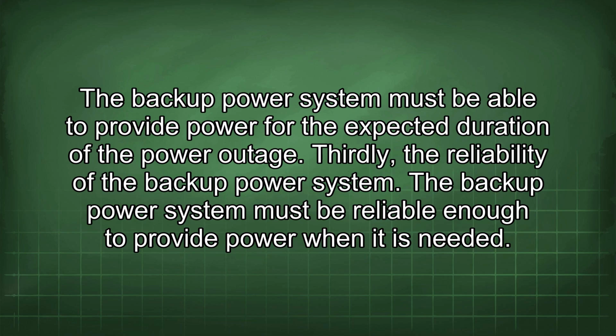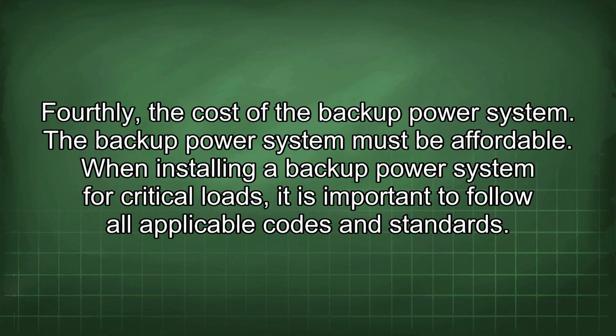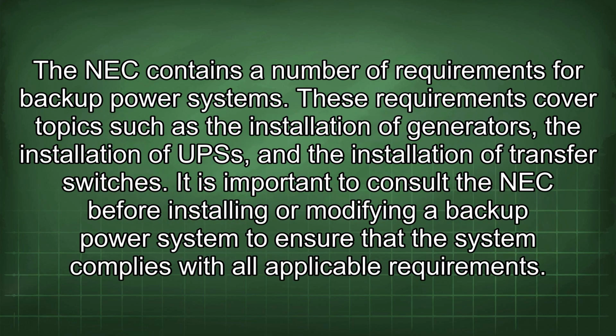Thirdly, the reliability of the backup power system. The backup power system must be reliable enough to provide power when it is needed. Fourthly, the cost of the backup power system. The backup power system must be affordable. When installing a backup power system for critical loads, it is important to follow all applicable codes and standards. The NEC contains a number of requirements for backup power systems. These requirements cover topics such as the installation of generators, the installation of UPS, and the installation of transfer switches. It is important to consult the NEC before installing or modifying a backup power system to ensure that the system complies with all applicable requirements.